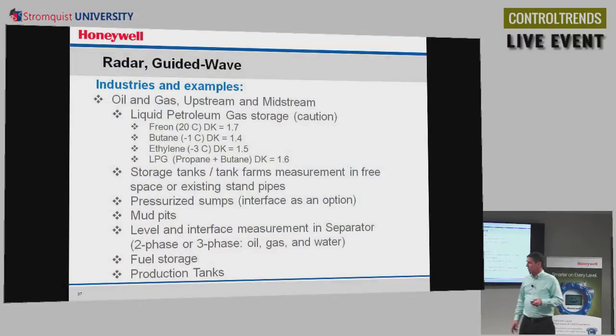Moving upstream and midstream, so this would be pipelines and at the well sites. Often for these light end hydrocarbons like freon, butane, and ethylene, their dielectric constants are low. So we'd want to be careful when we're getting down to the 1.4 area, but this is one we just want to approach with caution. Storage tanks, mud pits. These mud pits are used on drilling rigs. The level and interface measurements on separators. This is another kind of application at the well site. Fuel storage tanks and the production tanks. Production tanks, that was one of the examples we used in the application validation toolkit.